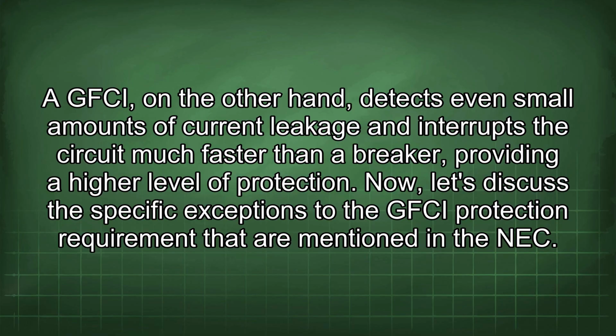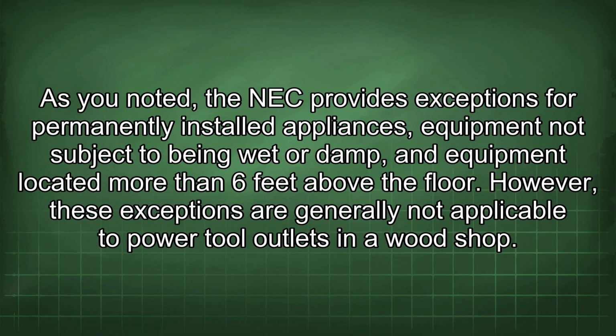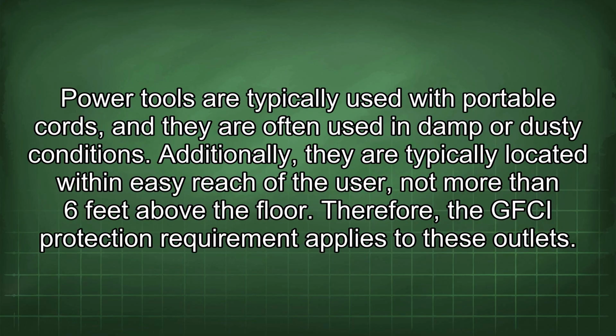Now, let's discuss the specific exceptions to the GFCI protection requirement that are mentioned in the NEC. As noted, the NEC provides exceptions for permanently installed appliances, equipment not subject to being wet or damp, and equipment located more than 6 feet above the floor. However, these exceptions are generally not applicable to power tool outlets in a woodshop. Power tools are typically used with portable cords, and they are often used in damp or dusty conditions.